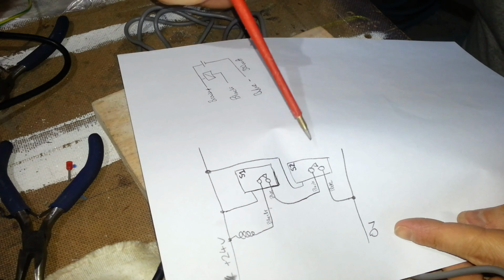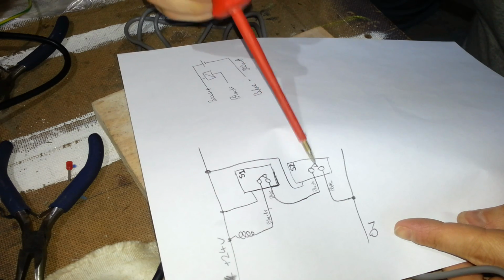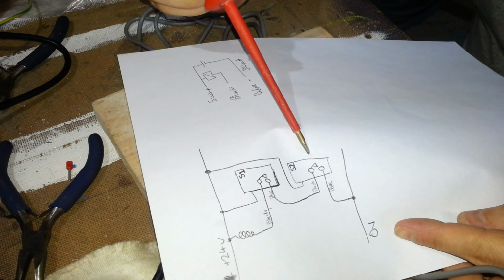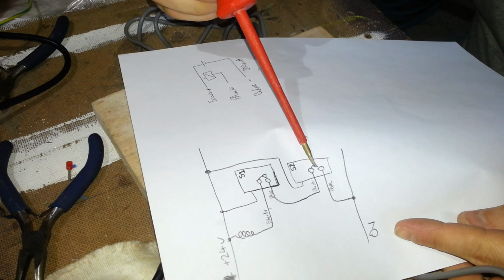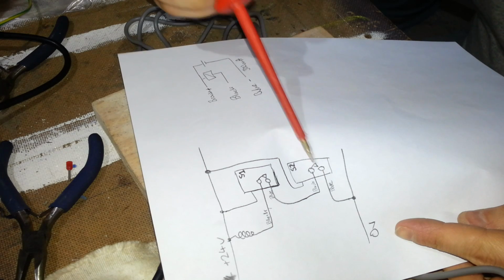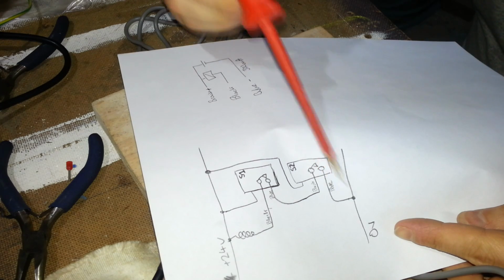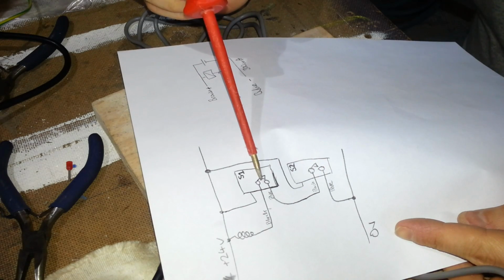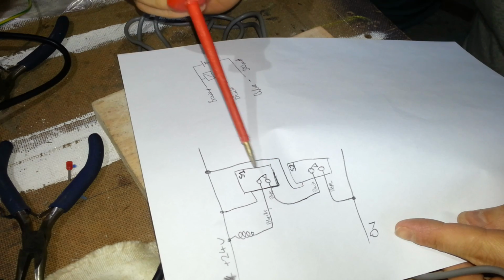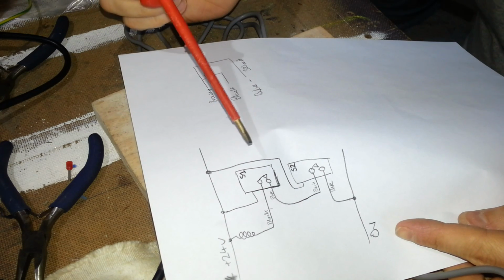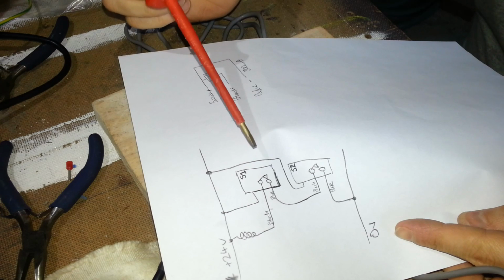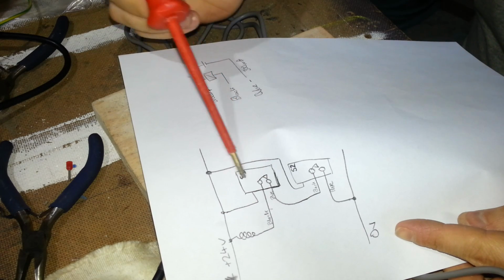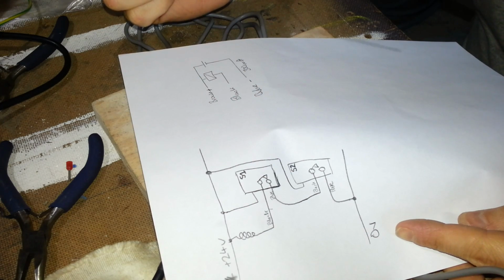But when sensor 2 is triggered, it's opening here and cutting the neutral for sensor 1. So sensor 1 is actually becoming de-energized. And therefore the lights go off on both.